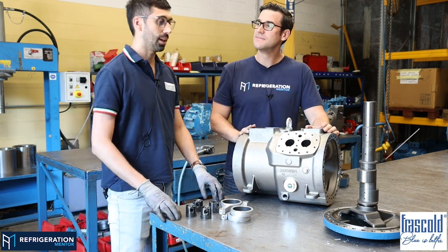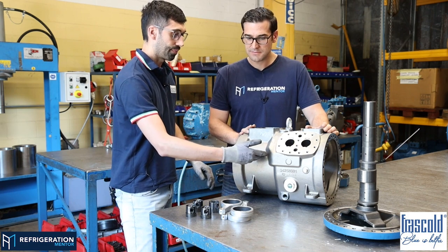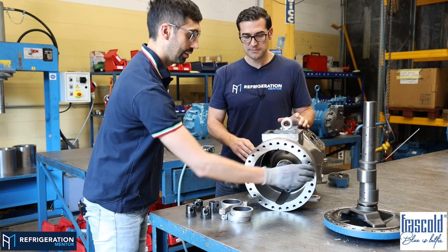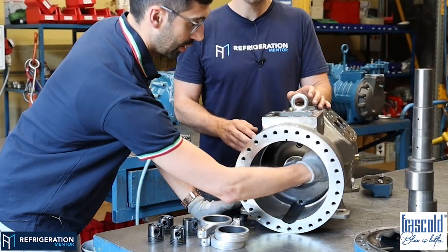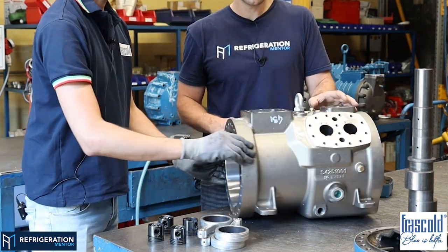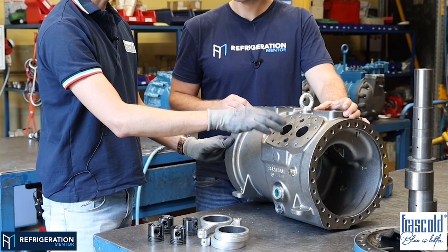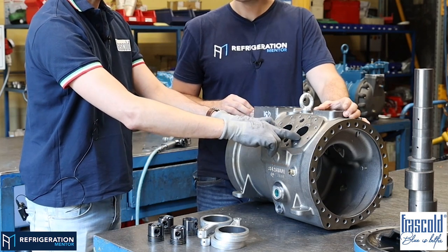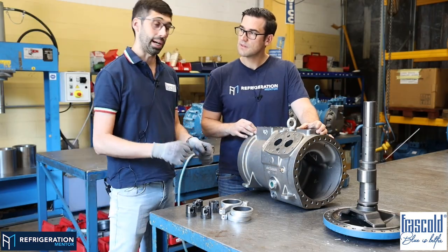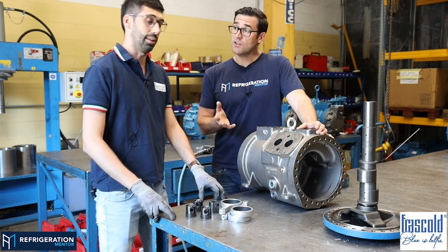Yeah. For sure, but the most probable outcome will be the suction of droplets of liquid refrigerant directly into the internal conduits here, this way, on the upper side, this way, ending here. And if we bring liquid droplets to the suction port of our valve plates, we will face for sure a liquid slug inside the compressor chamber with the smashing of the suction reed valves.